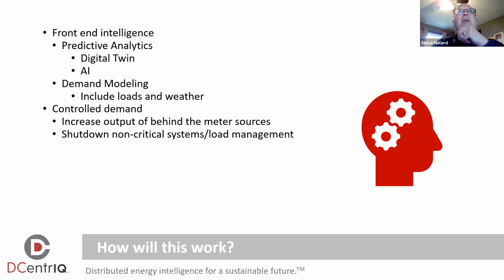I can also use it to shut down non-critical systems and do load management. We're going to talk in a few minutes about the Buboltz Nature Preserve up here in Appleton and the microgrid we've installed there. An important component of that microgrid isn't just that we supply power to the site, but that our microgrid integrates with their facilities. So if we know we're going to be short on energy, we can interact with the building management system and tell it - hey, that booster coil you use to preheat air coming into the building on the makeup air unit, could you cut that back by 20 percent, please?